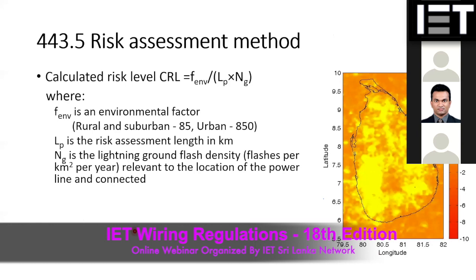Also, the new standard introduces a simplified version of the risk assessment. Normally overvoltage protection is covered under lightning, IEC 62305, but that is adapted in BS 7671, and a new simplified risk assessment is given here. When you are designing any new installation, you have to calculate the risk level, the risk of transient overvoltage, and depending on the risk level, you have to put transient overvoltage protection devices.